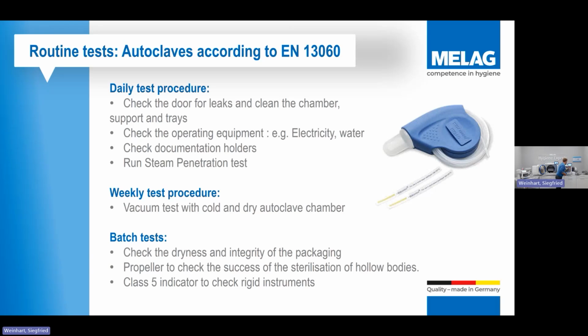So it'd be generally the first program you do first thing in the morning, once a week. Run that vacuum test, everything comes out of it. So it's a cold chamber only. It takes about 5 minutes or so, depending on the manufacturers. Run it, it'll give you a readout. Has it passed? Has it failed?